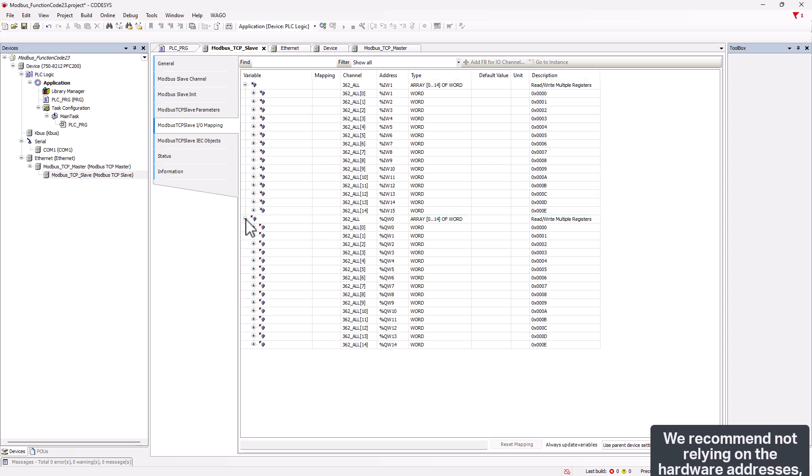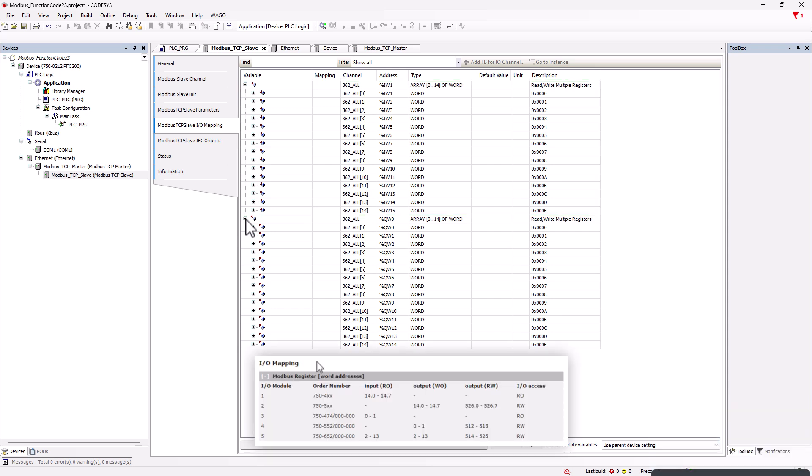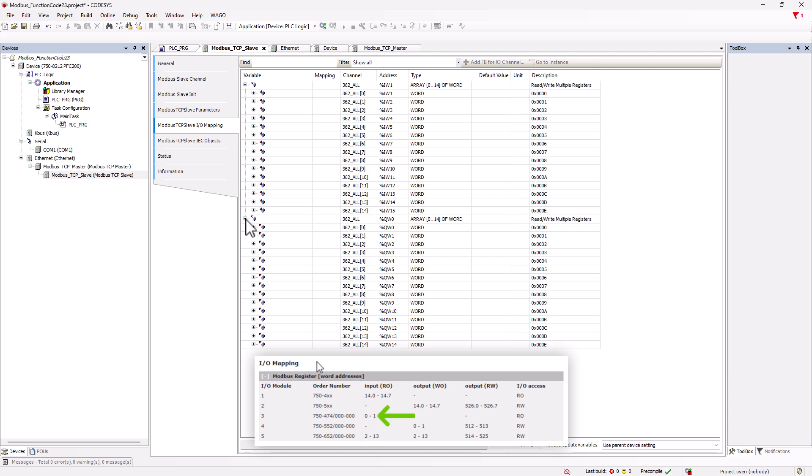Assigning which word belongs to which module is now quite simple. If we open the list of Modbus registers from the WBM of the coupler again, the word addresses listed here correspond 1 to 1 to the channel numbering. Word 0 and word 1 are the two analog inputs, which are usually captured with one word variable each.